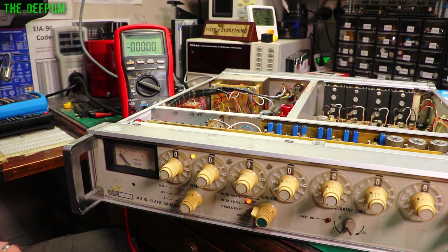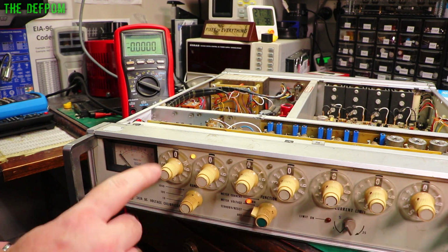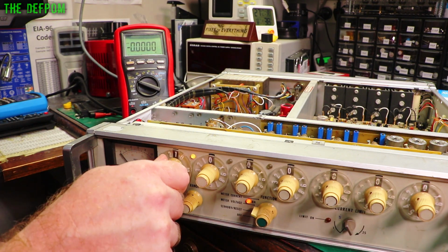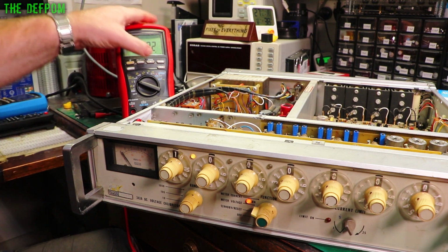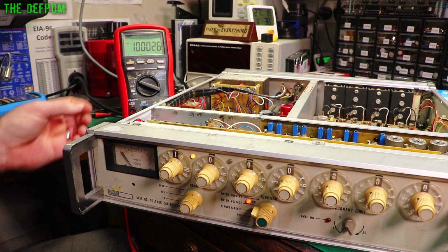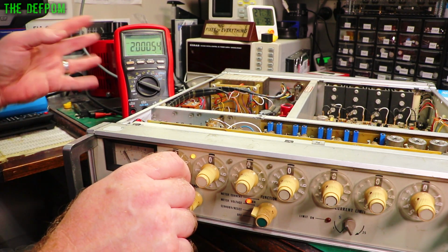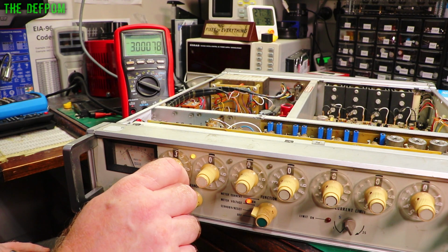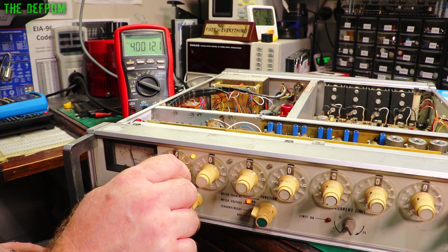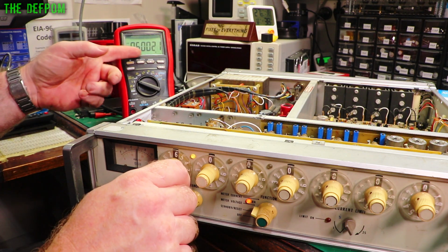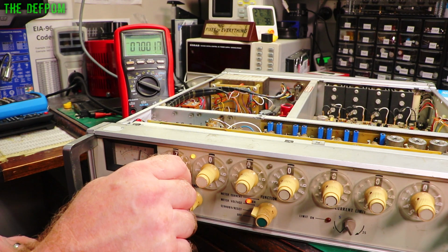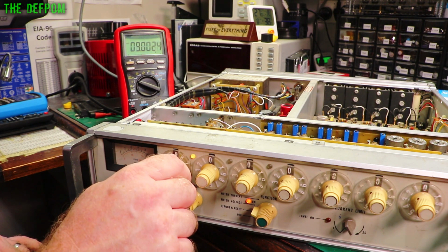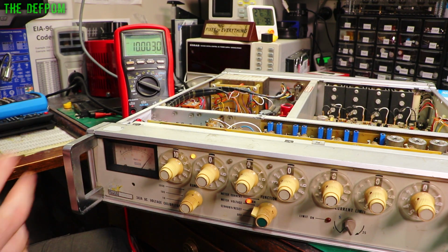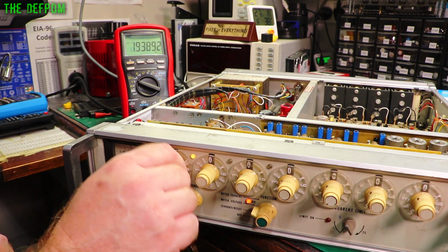Right, let's give this thing a try out. So 10 volt range, currently everything's set at 0. Output is on. 1 volt, not too bad. Let's increase the resolution. Obviously it's not going to be accurate because it's all just turned on. 3 volts, yep. 4, slightly off there. 5, but it could be calibration issues on this rather than the actual calibrator. So I'm going to check the decades, that's it, so 10 volts, yep, all those decades are working.